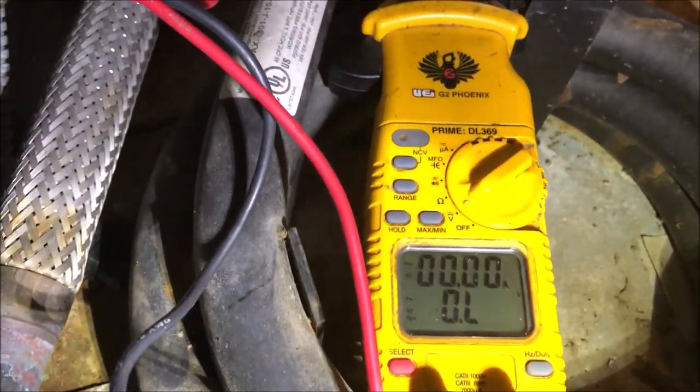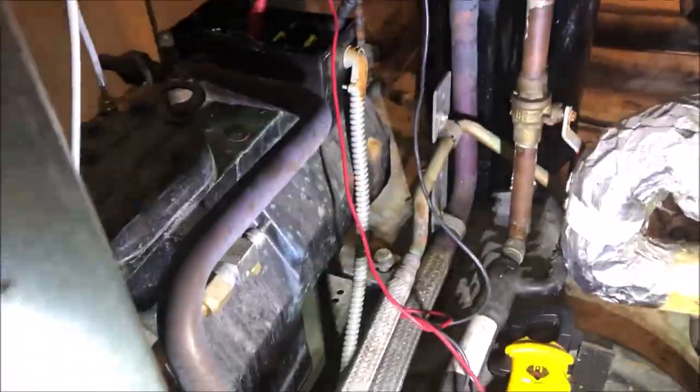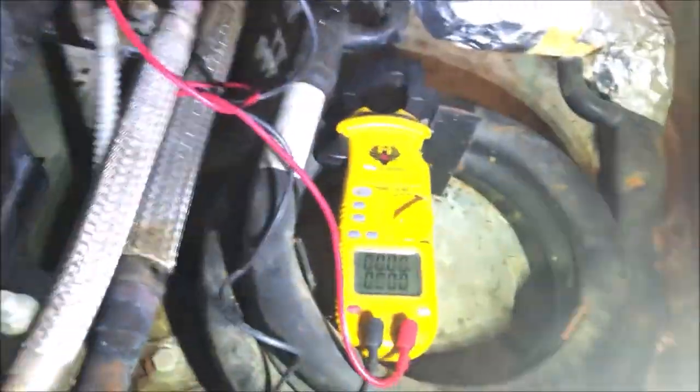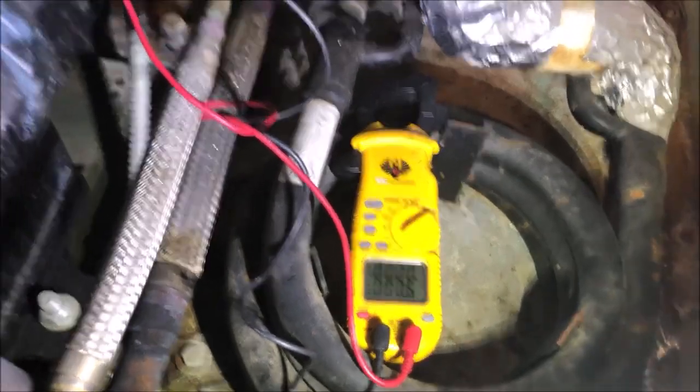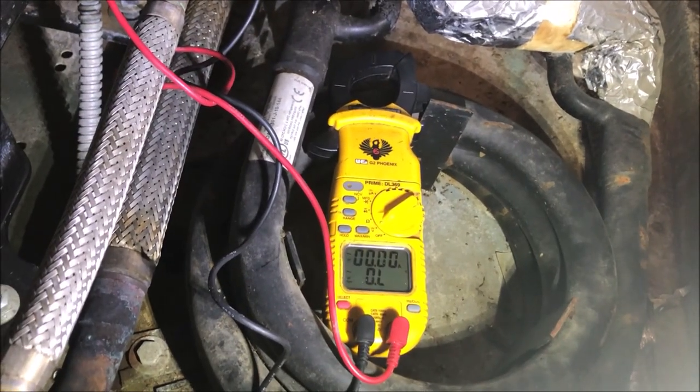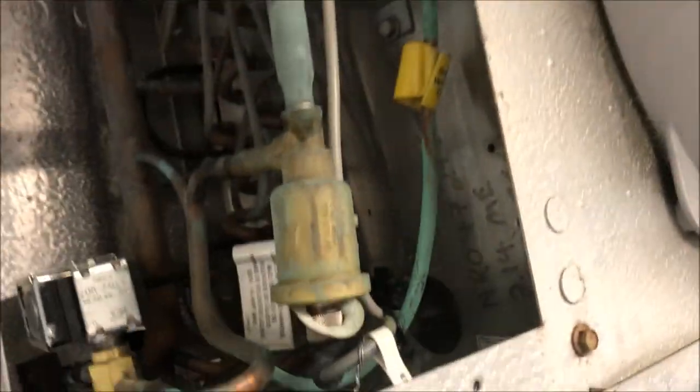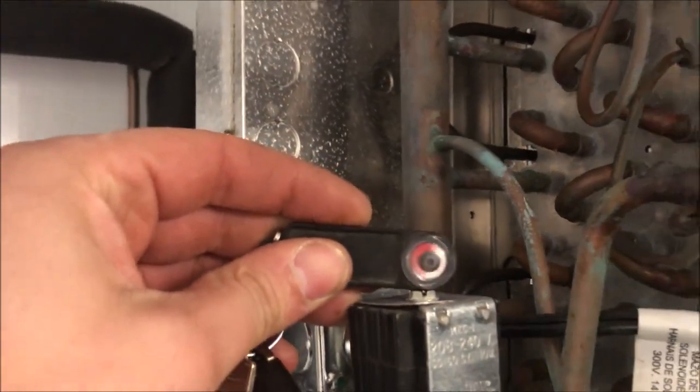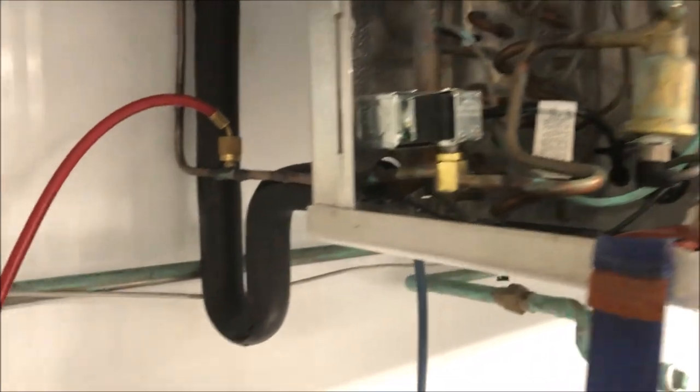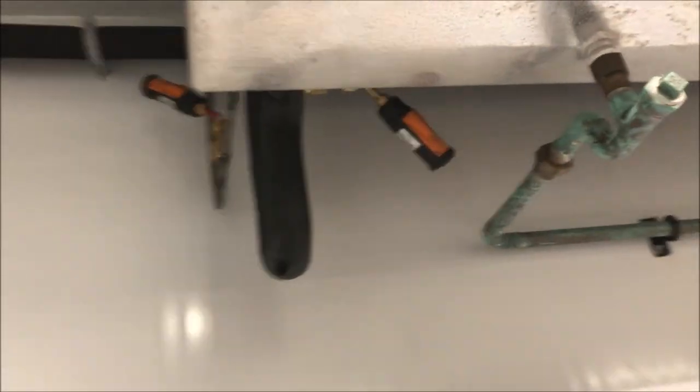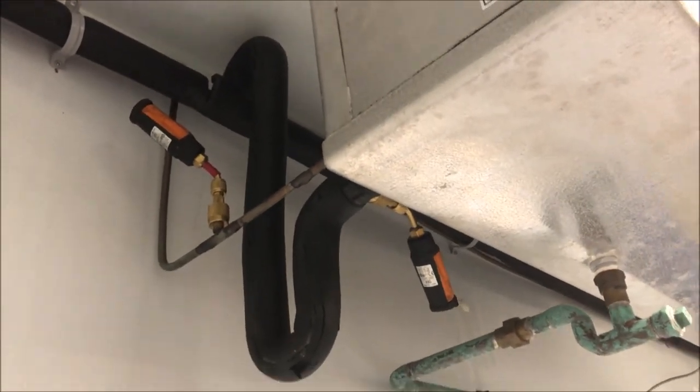I have to test it really quick or else I'm going to trip the breaker downstairs. We got to work smart. We're getting 194 volts there, let's go to our next combination. Getting 194 volts and let's check our last combination, make sure we're not dropping a phase. And we're getting 194 volts, so our voltage is dropping because our amperage is so high there, 65 amps. So you can see we have a call for cooling. What I'm finding really strange is my pressures are 145 and 308. That's with the compressor off. We should be equalized right now or attempting to equalize, so our pressures are insanely high.